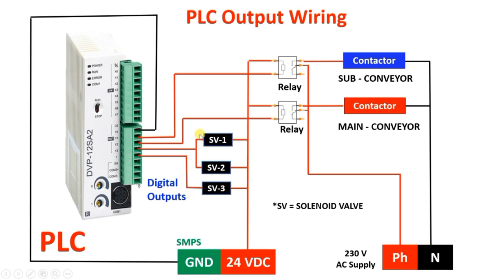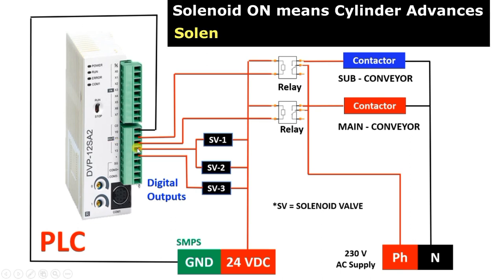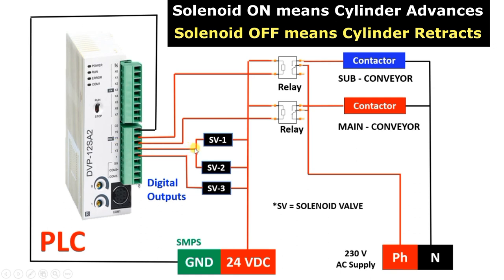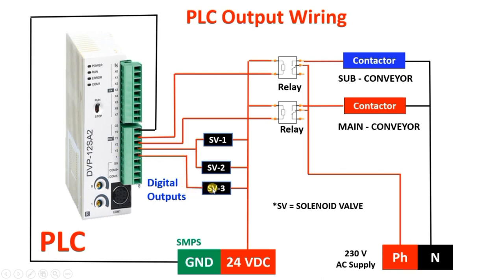For the packing machine, there are three solenoid valves and three pneumatic cylinders. Two outputs Y2 and Y3 are used. From Y2, one output activates two solenoid valves — both solenoid valve terminals connect to Y2 and 24V respectively. Y3 connects to solenoid valve 3 similarly. When Y2 is on, both cylinders advance; when Y2 is off, they retract. The same operation applies to solenoid valve 3.